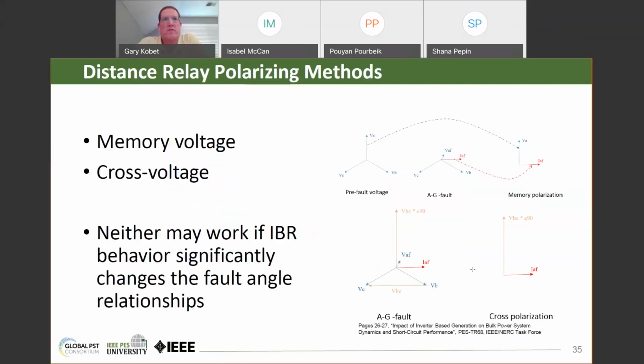Some other aspects of protection can be affected by inverter-based resources: polarizing methods for distance elements that rely on memory voltage or cross-polarized voltage. If the fault angle relationships change significantly during a fault, if the fault current angle changes significantly during a fault, then the polarizing for the distance element may not be as reliable. Next slide, please.